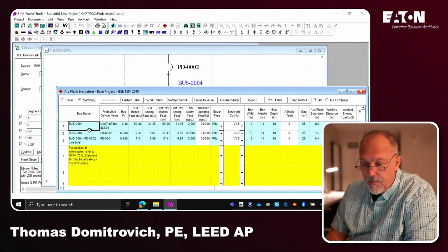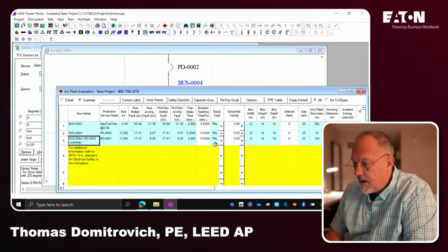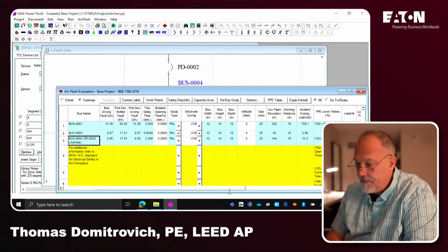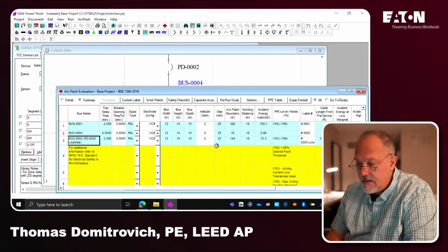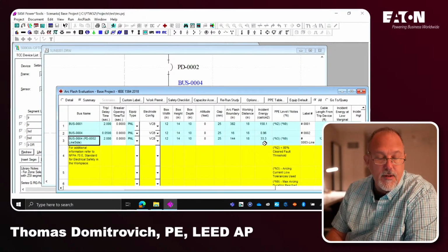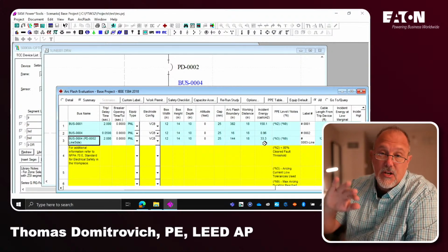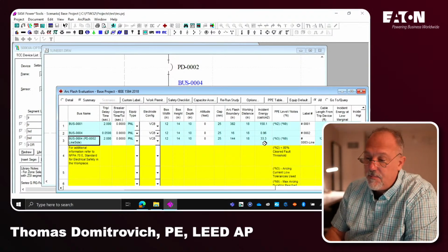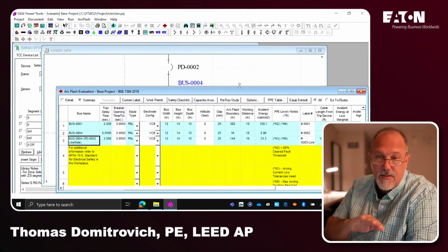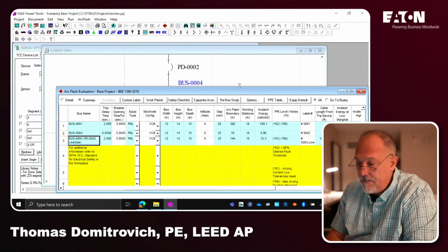So for panel 4, based on line side propagation, our calories are 33.3. You see that? Right there, 33.3. So that's our calories per centimeter squared. And that's because the protecting overcurrent device is not on the secondary, it's on the primary.